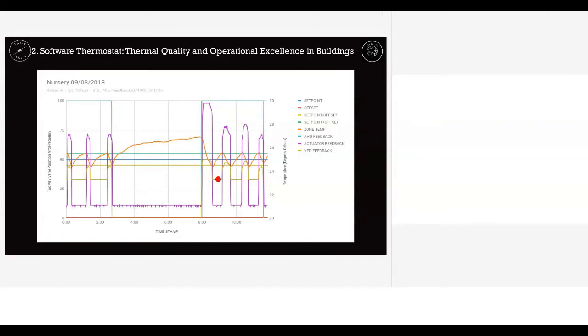If the area is comfortable, as you see in this particular area, this is the two-way valve position and feedback. At the same time, this orange line that is oscillating is the area temperature. This is the upper limit and this is the lower limit. The temperature axis extends from 20 to 30 and we are playing between 24.5 and 25.5. The upper and lower limits are the comfort requirement of the area. This is also a nursery AHU where small kids are there. They don't want too much cold and they don't want too much heat. So the set point is 25 degrees and the offset, that is the range of modulation, is 0.5. It is modulating between 24.5 and 25.5.